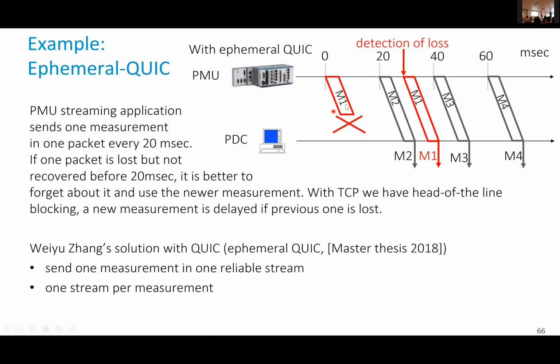The effect is that if measurement M1 is lost, it will be retransmitted by QUIC, but if M2 arrives first, this will not block at the receiver, which is the desired behavior. This is what we would like for the PDC side - we leave it to the PDC to decide whether M1 is useless or not. It depends on time alignment. Perhaps M1 is still useful because the PDC is waiting for measurements of this time period from others not yet received, or perhaps it's useless - it's the PDC that decides. Compared to using TCP, M2 would be invisible here until the loss of M1 has been repaired.